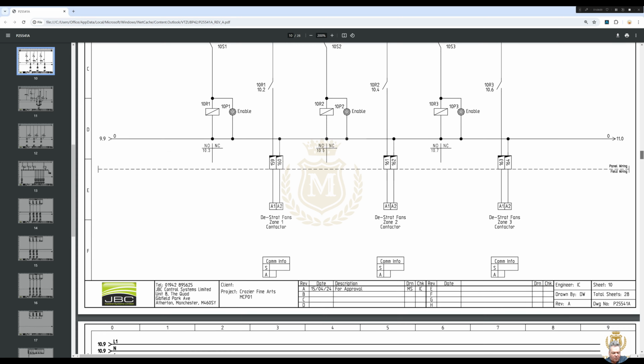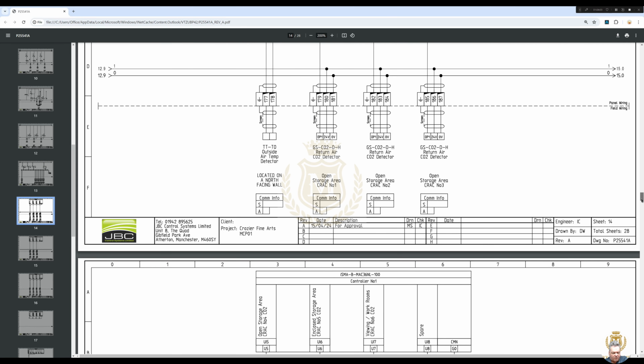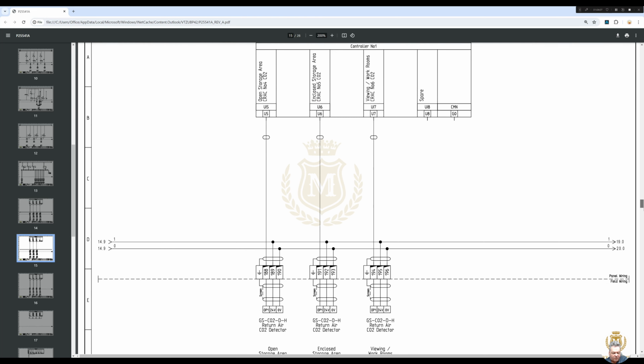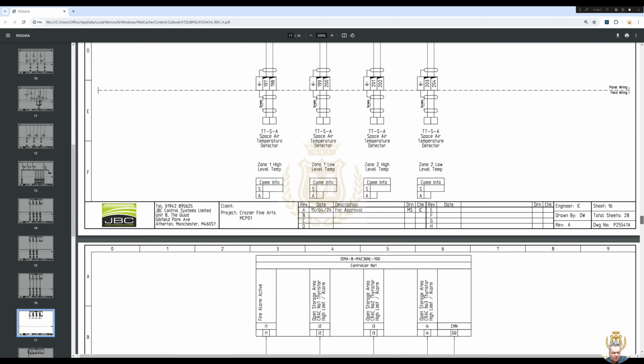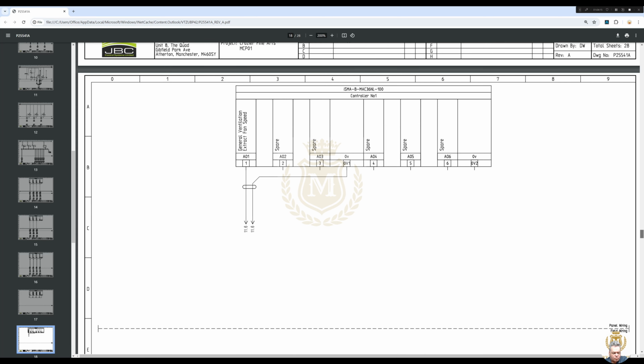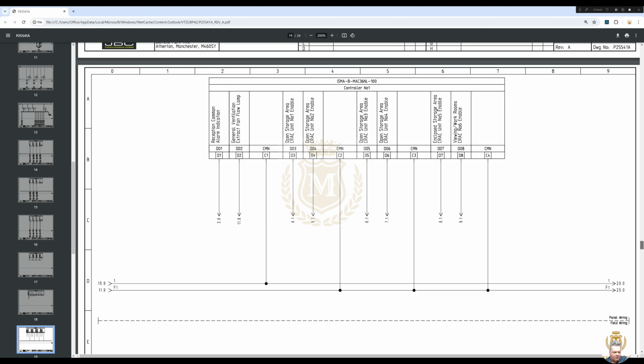So let's have a look at the IO. No, is there any point in looking at the IO, because I know there's no digital input. General ventilation extract fan speed. Yeah, we know about that. General ventilation extract fan flow lamp. Digital output 2. So I'm putting on DO2. General ventilation extract fan flow lamp.